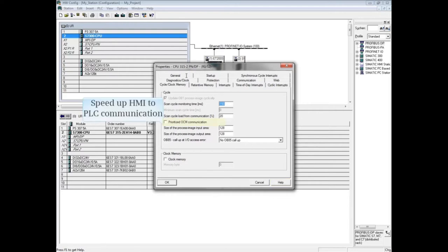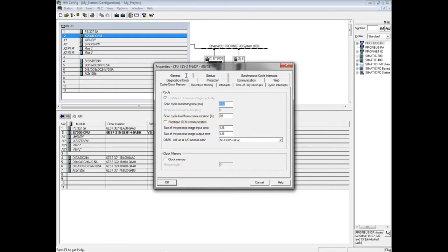Placing a check in the box for prioritized OCM communication will speed up communication between the HMI and CPU but does slightly increase the scan time. If the CPU does not support this function, the box is grayed out.